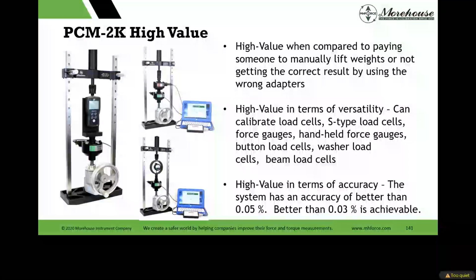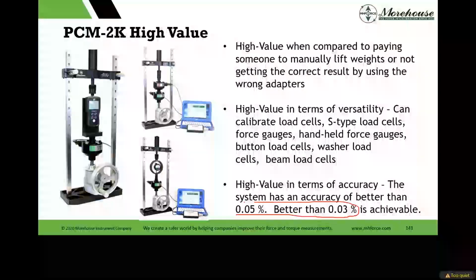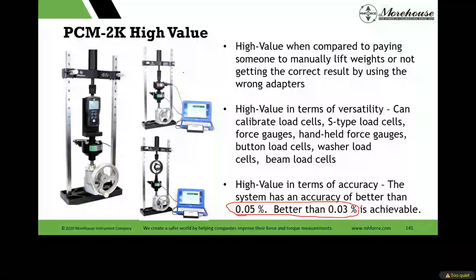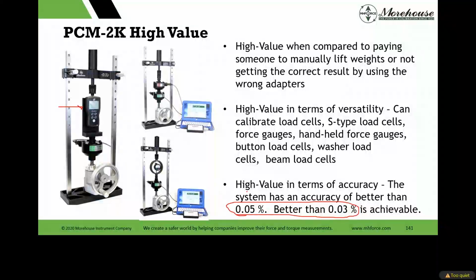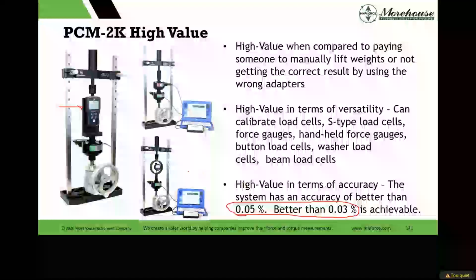This is some of my marketing lingo, but if you're looking at doing low force and cannot afford dead weight machines, these are really good machines overall. In terms of accuracy, you basically get uncertainties of about 0.03 to 0.05, depending on what you want to do, and that's good enough for most applications. Certainly good enough to do these, which are 0.1, so you'd be 2 to 3 times better than that.